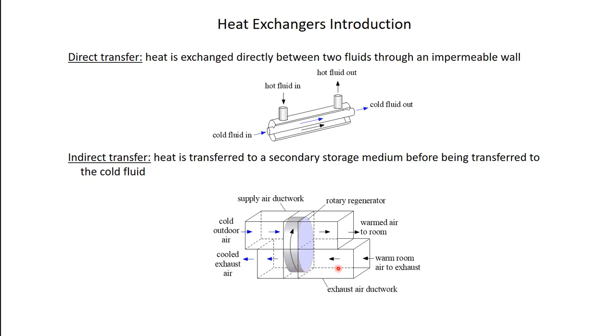This is an indirect transfer heat exchanger. The warm air coming out of your house flows through a big spinning wheel. The wheel spends some time in the warm air duct and some time in the cold air duct. It's full of little holes that the air flows through, so the warm air warms up the wheel material. As the wheel rotates into the cold duct, the warm material transfers energy to the cold outdoor air, warming it up. Then the cycle repeats. The warm air is not transferring energy directly to the cold air; instead it transfers energy to the wheel material, and the wheel material transfers to the cold air.